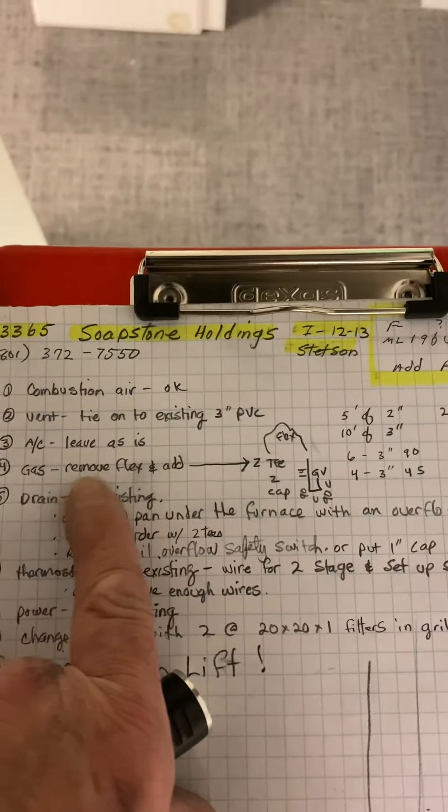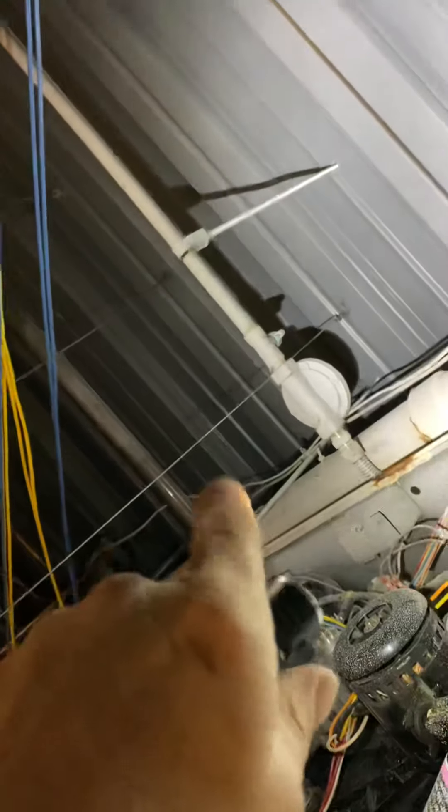For the gas, we're going to just remove the flex. This gas line hangs down a little bit, so you can probably pull it up once you cut the flex, pull it up and level it. From there, add a two-inch T with a two-inch dip leg, and then flex up the top and to the furnace.